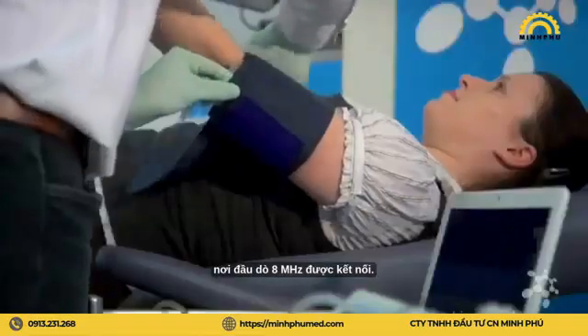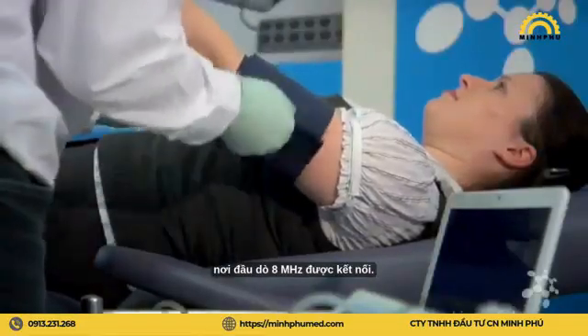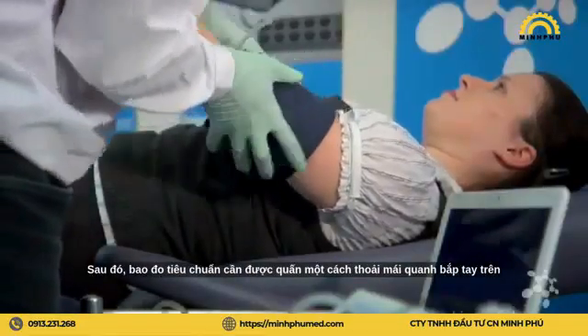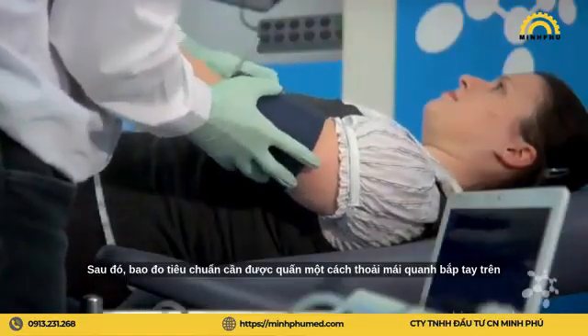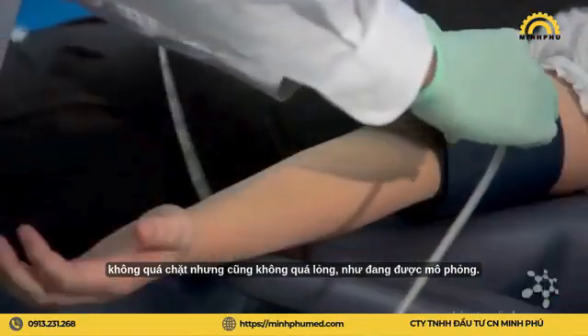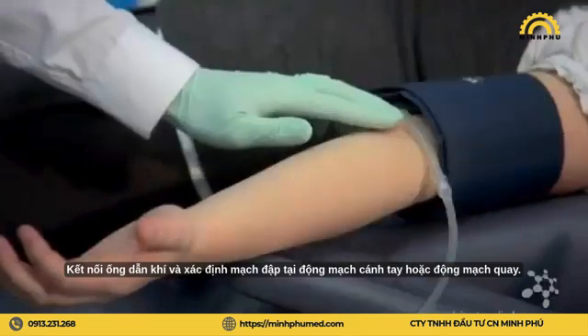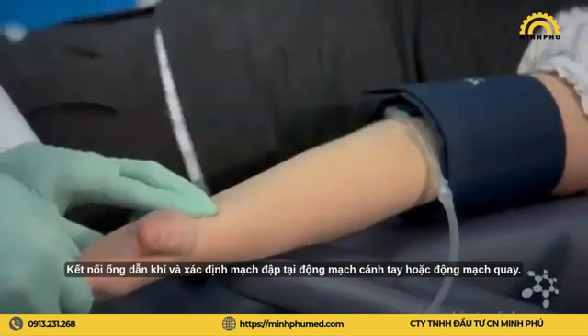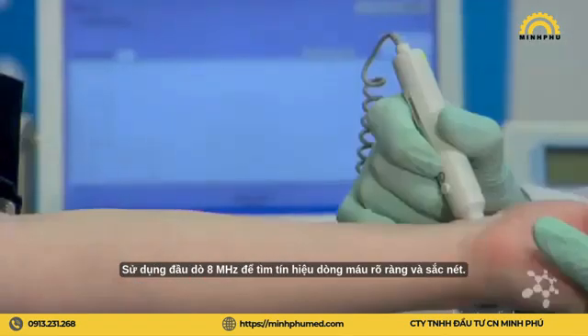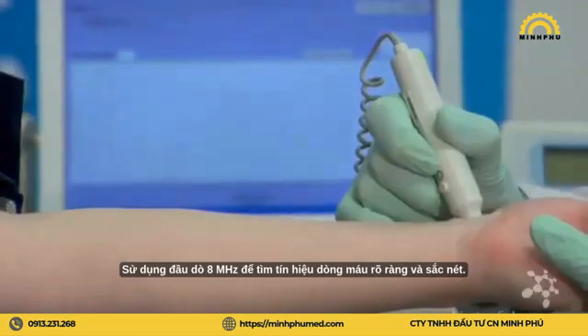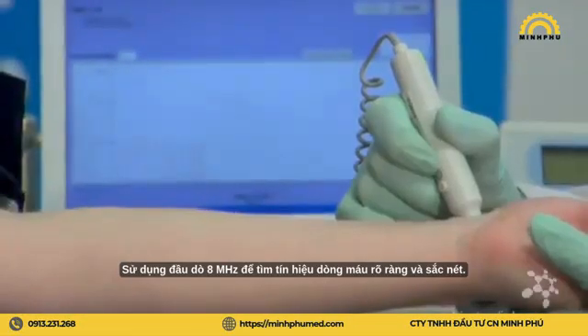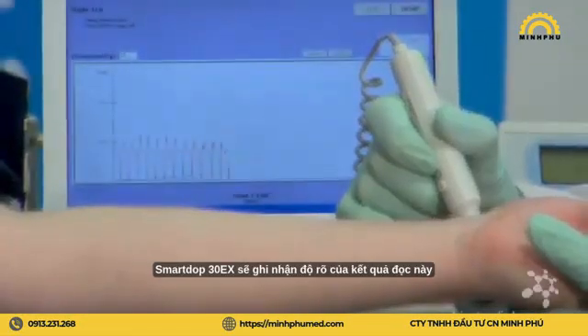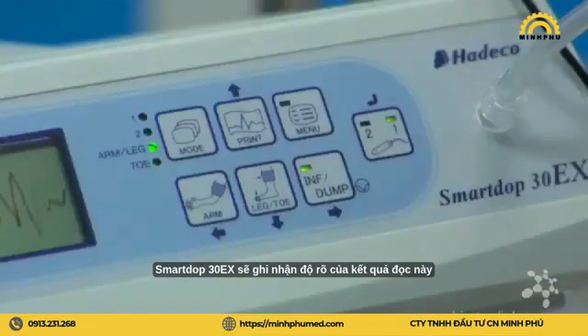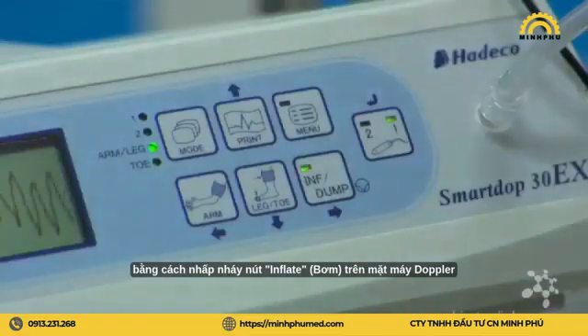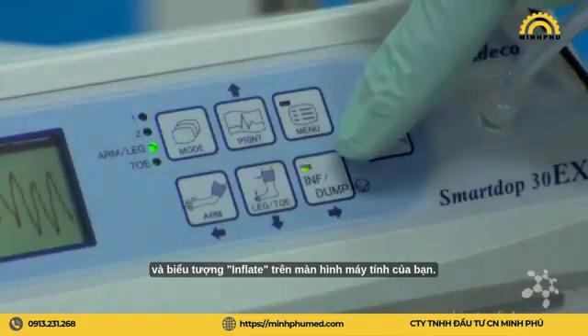The standard cuff then needs to be comfortably wrapped around the upper arm. Not too tight, but not too loose either, as demonstrated. Couple up the air tube and locate a pulse at either the brachial artery or the radial artery. Using the 8 MHz probe, locate a nice, clear and crisp blood flow. Smartdop 30 will acknowledge the clarity of this reading by flashing the inflate button on the face of the Doppler and the inflate icon on your computer screen.